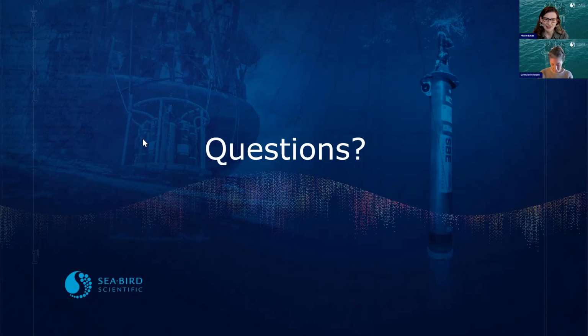And then Robin is asking, even if we don't notice any drift in our sensors, should we still send in our equipment to be checked and repaired after every field season? So best practice is to evaluate the use of your sensor against the data need that you have. It's very application dependent. Some folks are using their equipment rough, and you can look at it and tell. They're using them in high fouling environments. They're using them in just difficult to control conditions, so they're seeing a lot of physical interactions. They're seeing a lot of biological interactions, and those would be applications where we would recommend more frequent maintenance.